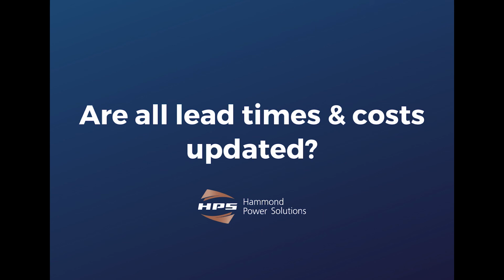The lead times and cost, good question, because we've seen some massive changes in cost and lead times. No, the calculations that we did were actually done about 12 months ago. However, to the best of our knowledge, the cost for both liquid and dry type have scaled relatively the same. So while the cost may be a little bit different, the end result would be, for the most part, equivalent today as it was a year ago. The calculations that we did for the energy efficiency should be pretty apparent today. The cost of electricity has not changed that much in the past 12 months.